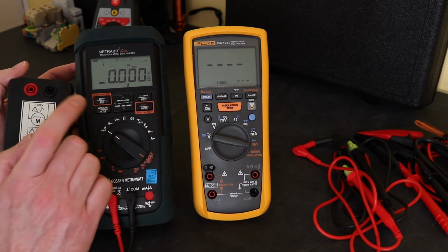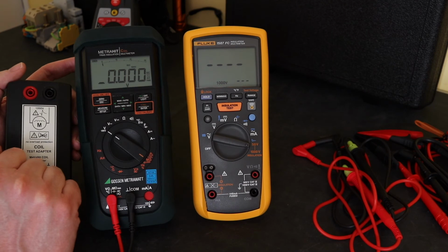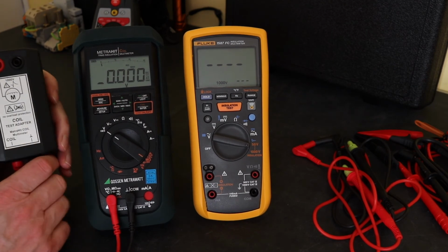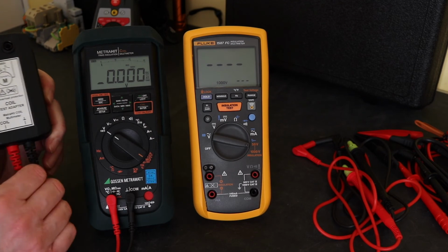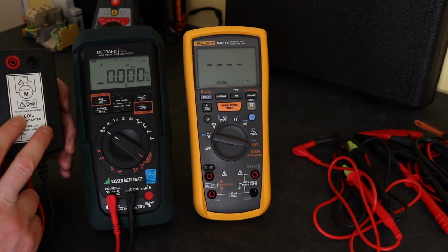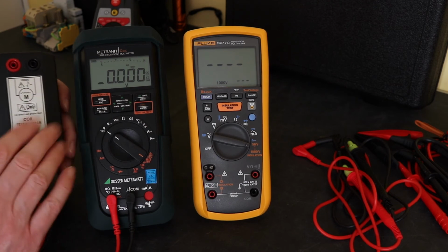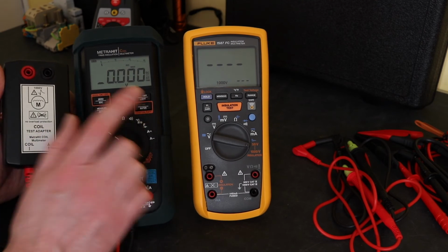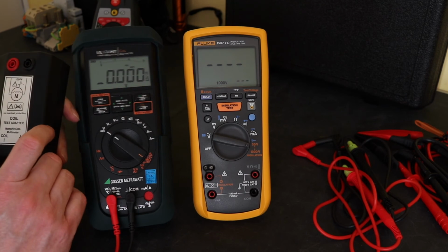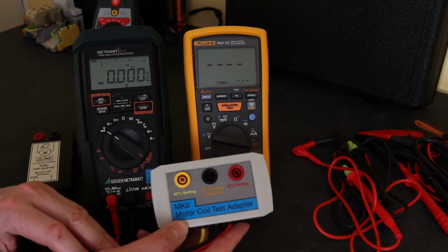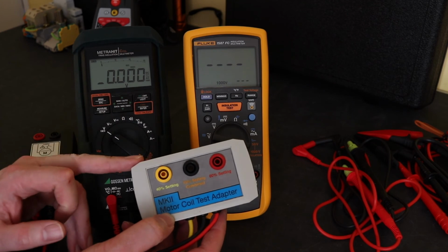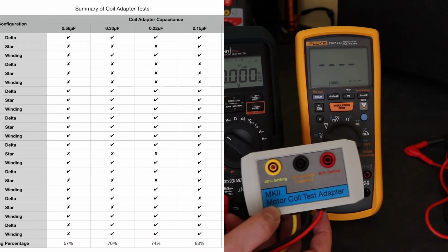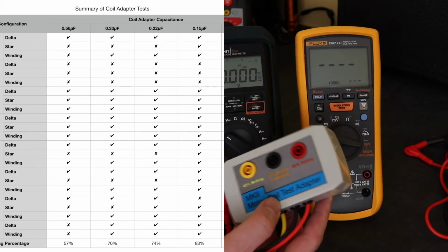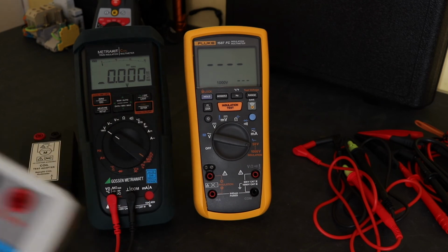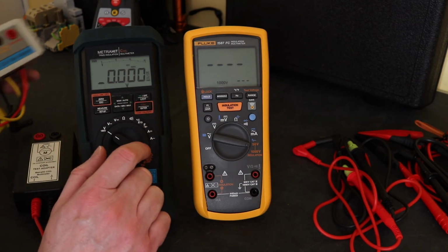So even with this test as well, you've got to try and remember the actual value before you stop the test. In regards to the functionality of this, again it's on the other videos, I've found this to have very erratic behaviour. I've emailed Gossen Metrawatt asking them for a different adapter, giving them all my motor details. I've even asked them about being able to lock the insulation test on. Gossen Metrawatt do not appear to want to talk to me, so I am none the wiser. So in the end I got that fed up with it, I built my own little test adapter up, that solves, I guess, a good 90% of the issues I had with getting readings, but there are still a few motors out there that I can't get a stable reading on. And obviously this doesn't solve not being able to lock the tester on.